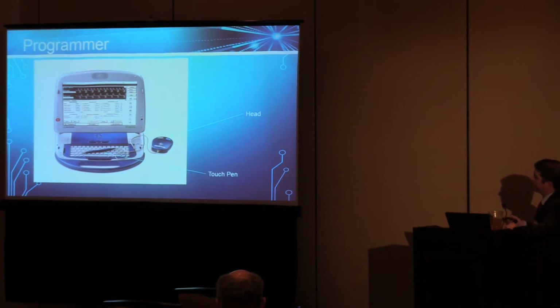Here's a typical programmer. This one's provided by Medtronic. Each of the programmers is unique to each of the manufacturers. We typically use 4 manufacturers: Medtronic, St. Jude, Boston, and Biotronik. But the main components of each of the programmers are similar. Usually there is a head or a wand, which goes over the pacemaker site, and a computer system, which allows us to communicate and talk to the pacemaker, make changes, and see what the pacemaker's been doing.